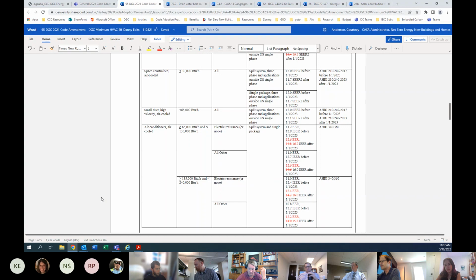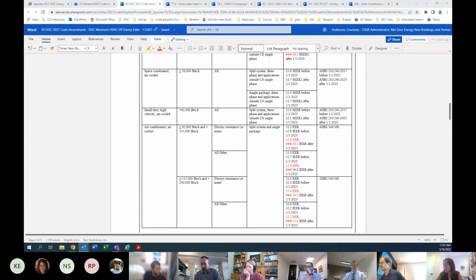So all of these numbers, where do they come from? They weren't just randomly picked. What I did, to recap, was look at the current AHRI database and select equipment efficiencies that were in the 80th percentile. So in other words, 20% of the equipment on the market should be a higher efficiency. Now that doesn't mean that 20% of equipment today are specified with higher efficiency, because these are used much less frequently. So these are high efficiency equipment, but they're equipment efficiencies that are available today. And if you could scroll down just a little bit more, please.